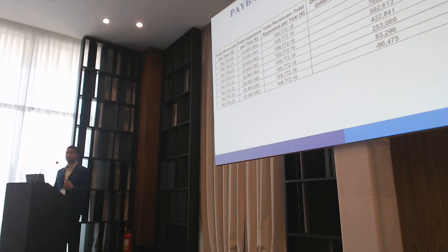Let's talk about the payback period of this investment. This calculation is based on the previous mission analysis and on the assumption that the annual maintenance cost of this system is 1.65% of the total investment cost. As you can see, the payback period of this system is 8 years. In the 8 years, this system provides 86,000 euros profit.